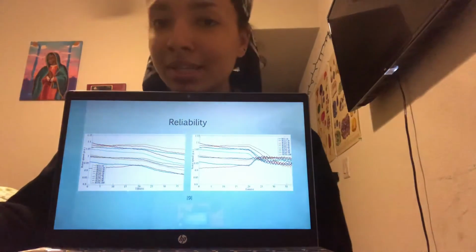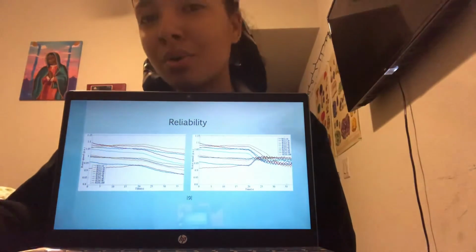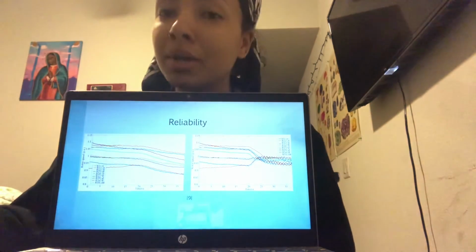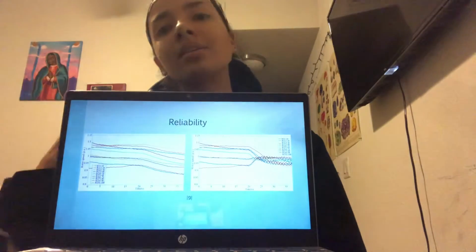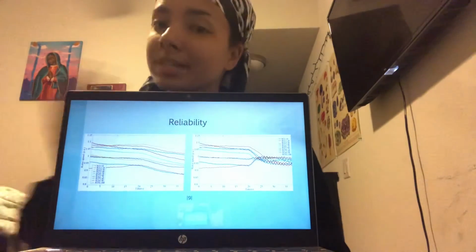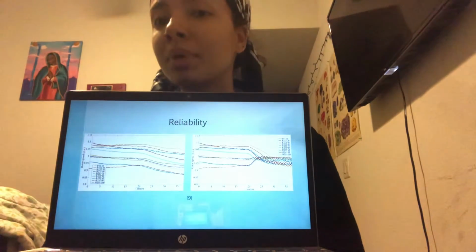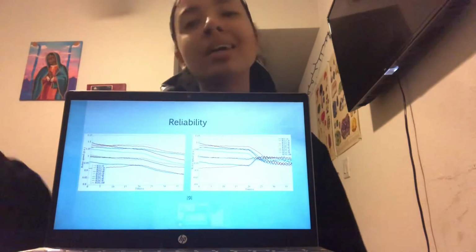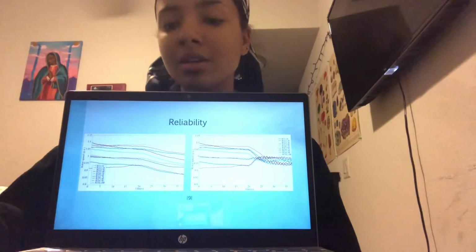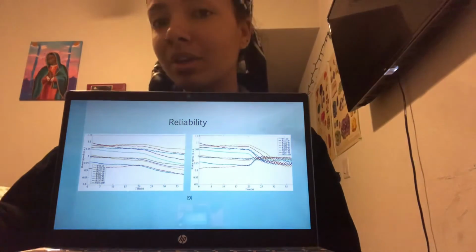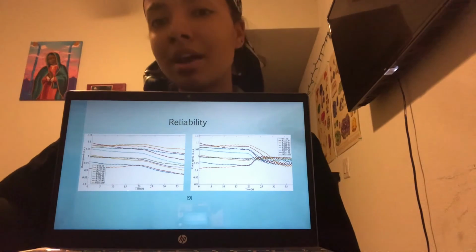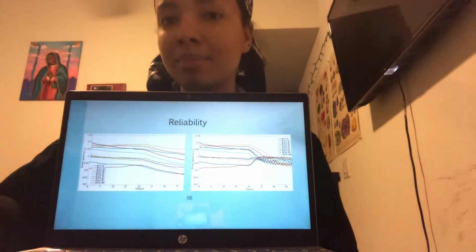It's also important to consider that inertial response on its own is very unreliable because it's hard to tell if a wind turbine will be able to contribute to the inertial response or not. For example, wind turbines that operate at their minimum rotor speeds or are operating along MPPT can't contribute to inertial response. So this leads to some error in calculating how many wind turbines are going to be operating in the system, which leads to error in calculating system stability.